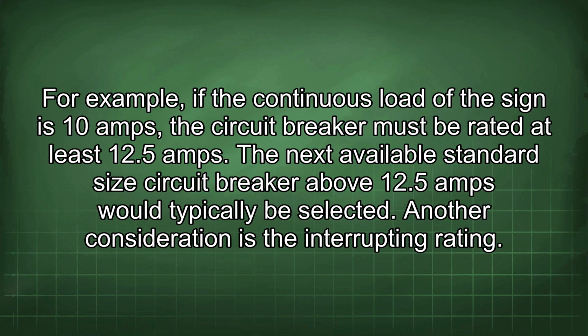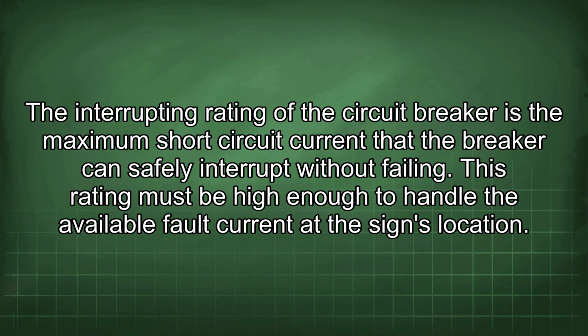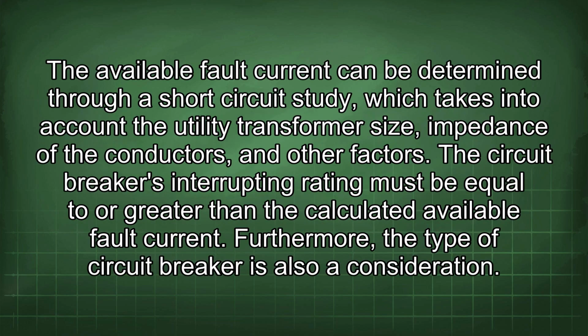Another consideration is the interrupting rating. The interrupting rating of the circuit breaker is the maximum short circuit current that the breaker can safely interrupt without failing. This rating must be high enough to handle the available fault current at the sign's location. The available fault current can be determined through a short circuit study, which takes into account the utility transformer size, impedance of the conductors, and other factors. The circuit breaker's interrupting rating must be equal to or greater than the calculated available fault current.